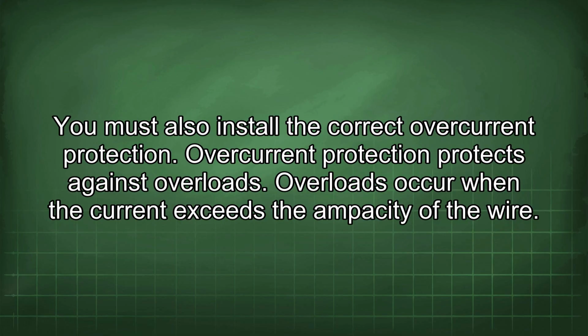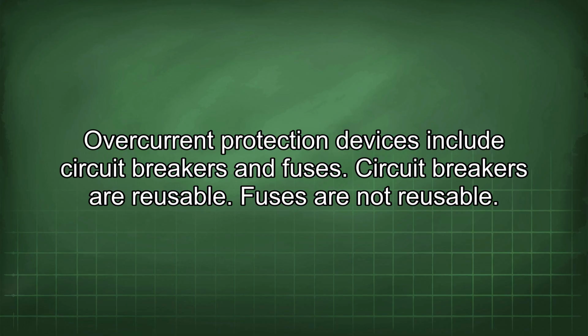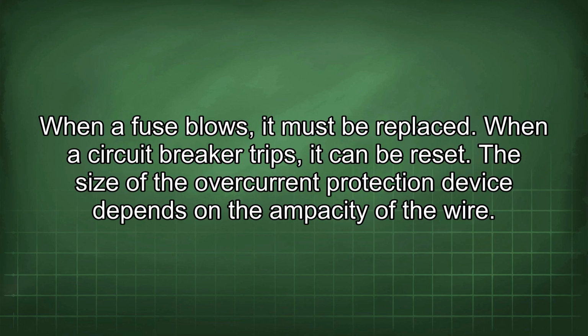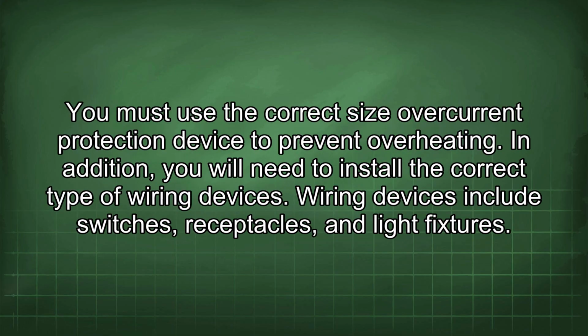You must also install the correct overcurrent protection. Overcurrent protection protects against overloads. Overloads occur when the current exceeds the ampacity of the wire. Overcurrent protection devices include circuit breakers and fuses. Circuit breakers are reusable. Fuses are not reusable. When a fuse blows, it must be replaced. When a circuit breaker trips, it can be reset. The size of the overcurrent protection device depends on the ampacity of the wire. You must use the correct size overcurrent protection device to prevent overheating.